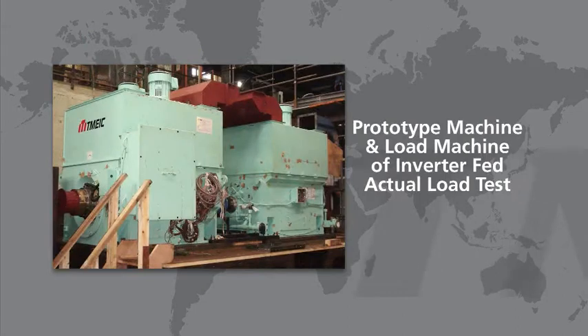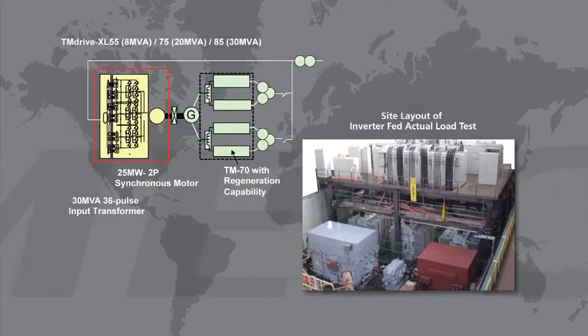Our prototype machines are tested at various speeds to verify the theoretical calculations. Here, a 25 megawatt synchronous motor is under test running at 3,600 RPM. Back-to-back tests are used to test large motors up to 25 megawatt size under full load. A large drive inverter supplies the motor while a generator acts as a load. Instead of wasting the generated power, it is fed back into the electric supply through another large drive.